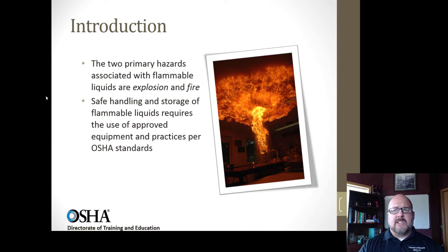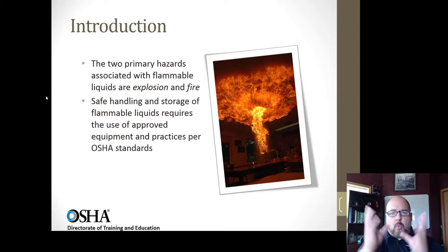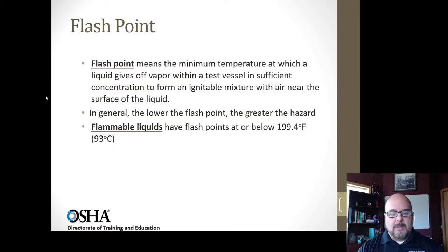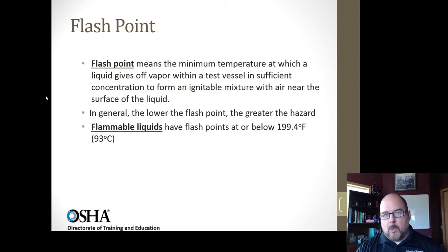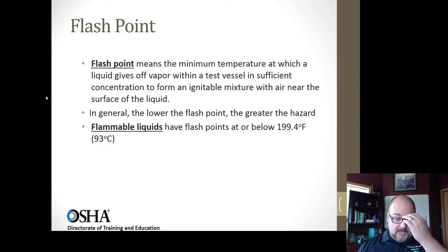Liquids with high volatility tend to put more vapor pressure into whatever device contains them. So if there's some sort of leak or fracture when it's opened, it rapidly releases and could be capable of either igniting or causing an explosion. The two key things to think about for flammable liquids are flashpoint and boiling point. The lower the boiling point, the more volatile it is. The lower the flashpoint, the quicker a release reaches its ability to ignite.